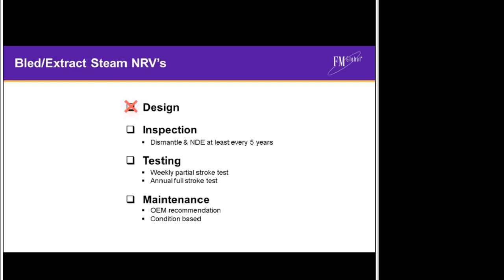The design of bled steam or extract steam non-return valves is a bit of a mixed bag. Historically, on large utility plants, this was well addressed, with most valves allowing online testing. However, smaller plants, such as waste-to-energy or biomass locations, often have passive non-return valves installed without even an indication to prove position. In these instances, it is not possible to visualize the valve moving or to test it, hence making it impossible to confirm that that valve is in an operable condition.